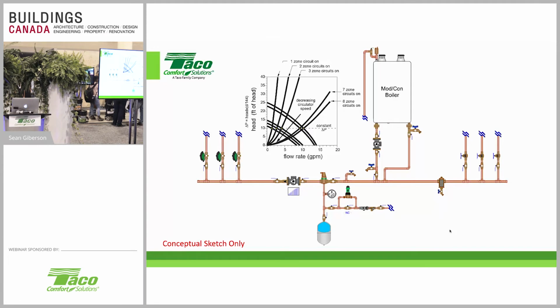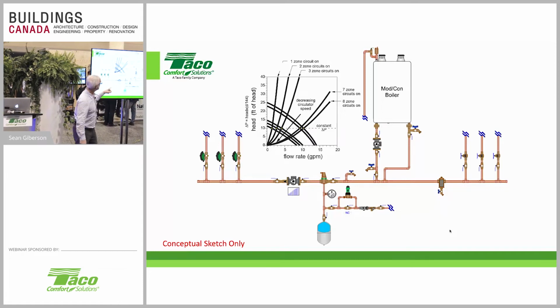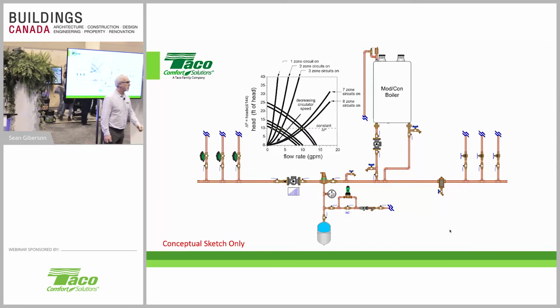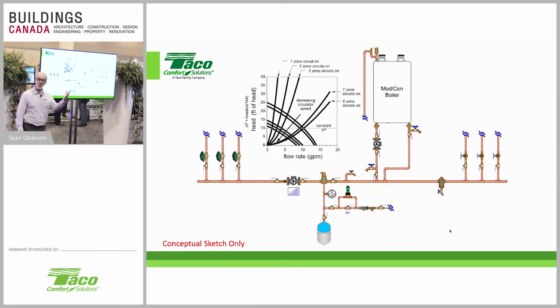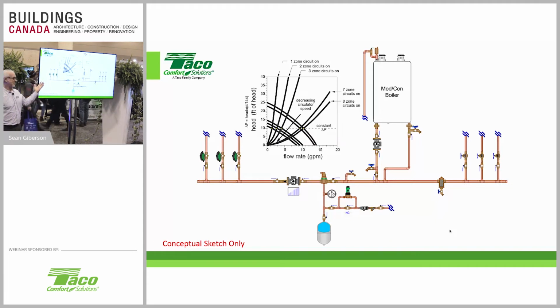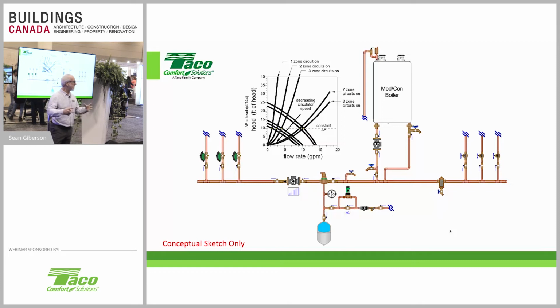Well, we'll just put a pressure differential bypass in. And that differential bypass really was a means to loop and make a shortcut from the supply back to the return. If there was too much flow, a spring valve opened up and it allowed that hot water to come back. What did we just do? We just threw energy away, right? We just took hot water back to a boiler, and what do today's boilers want? Cold water. The operating efficiencies from today's condensing boilers come from getting the coldest water, having that greatest band or that biggest delta T.